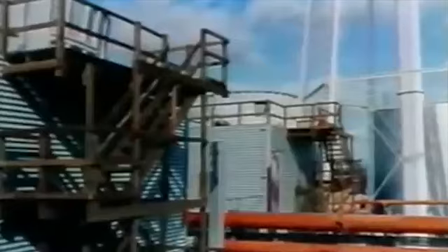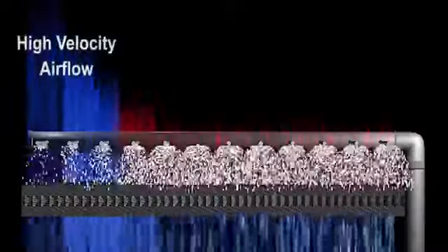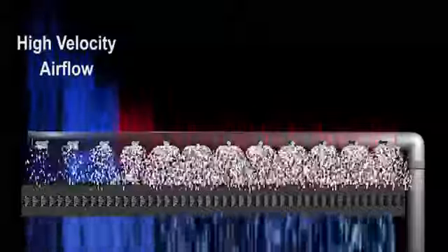In addition, aging and fouling of the pump system, improper orifices in the nozzle, fouling and or plugging of water spray nozzles, pump water being diverted to other processes, and under-designed pump capacity compounds the problem. Another side problem resulting from high-velocity airflow is enhanced drift loss, which wastes significant volumes of water.